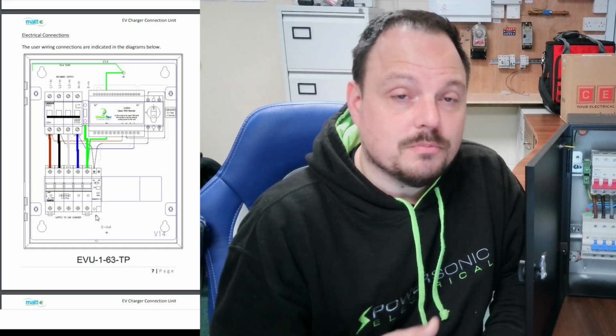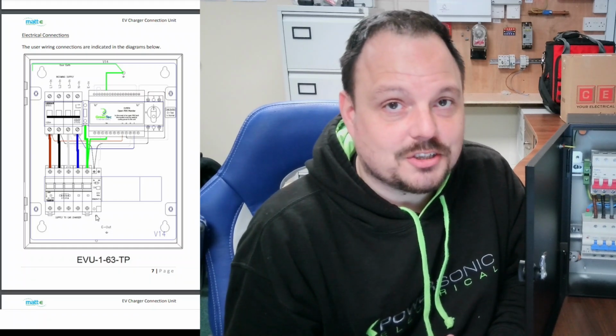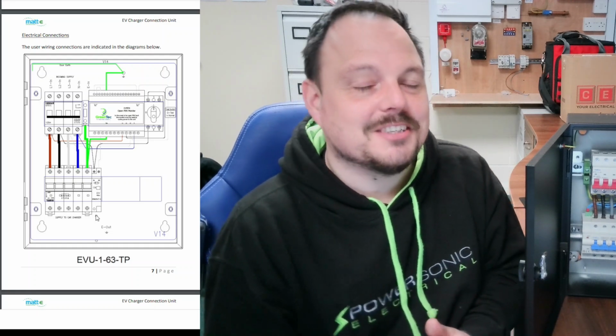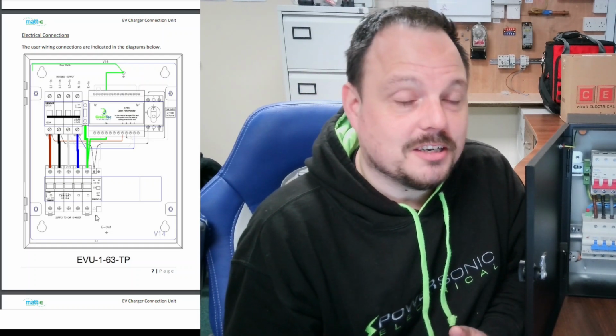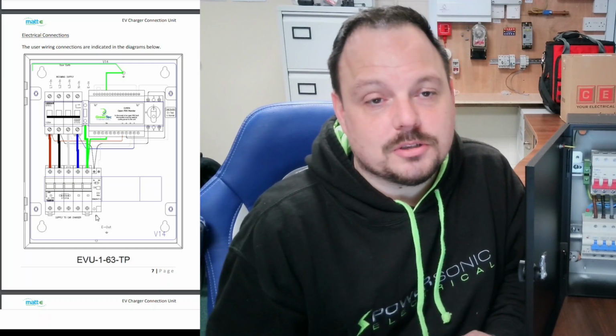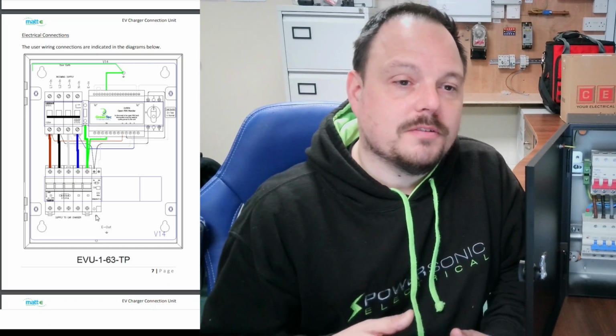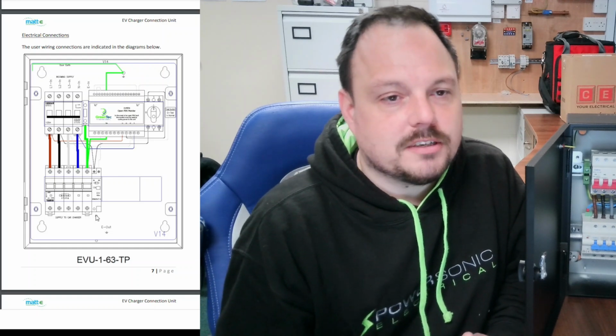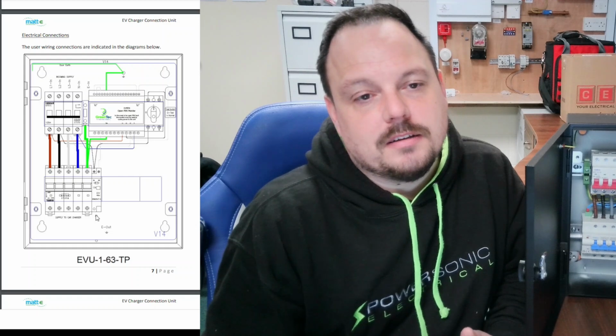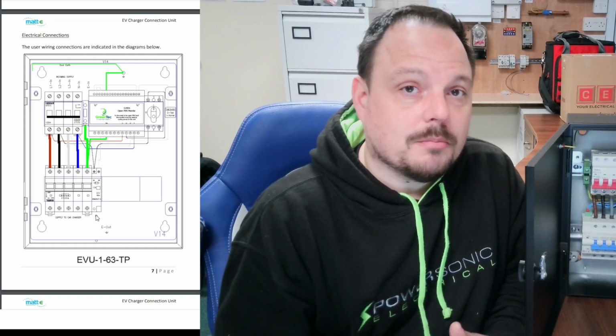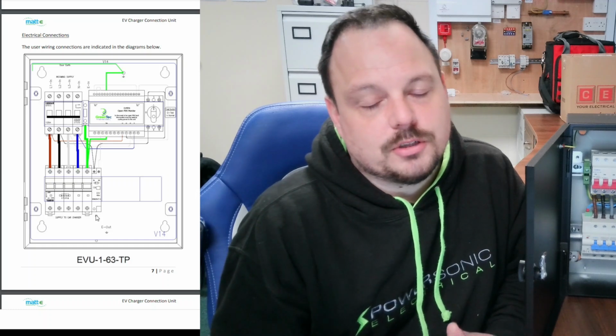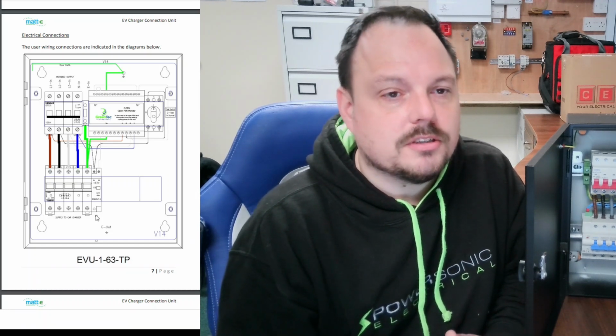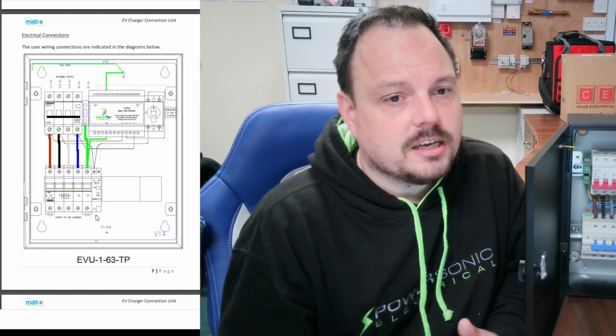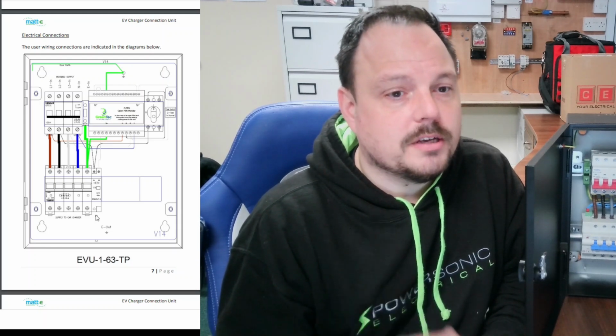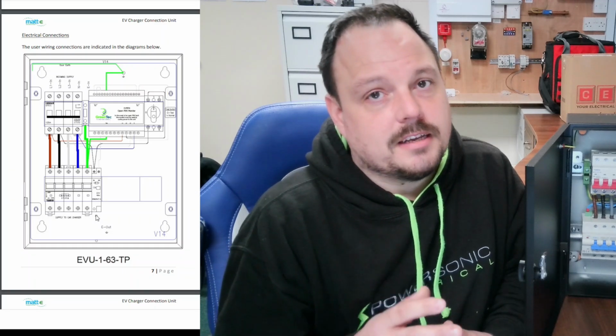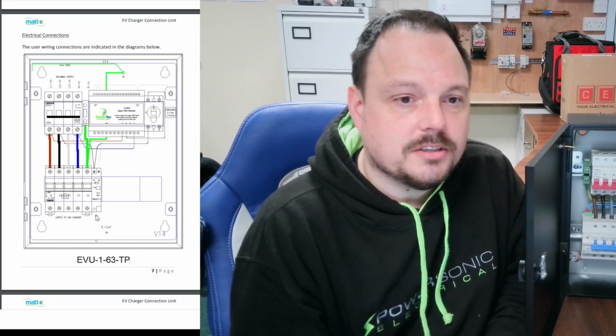And you can remove the chance of any of the metallic earth coverings causing you an issue if you use a cable that doesn't incorporate it to go out to the charge point. So people will use NYY, or you can use some of the specific EV ProCell cables, for example, the Doncaster Cables variant as well, where it doesn't have any armoring built into that, and you still have suitable mechanical protection leading to the charge points. So that's a decision for you as the designer and installer if you need steel wire armor. But if you do, make sure you consider the fact that you can export the earth bypassing all of these gubbins if you're not careful.